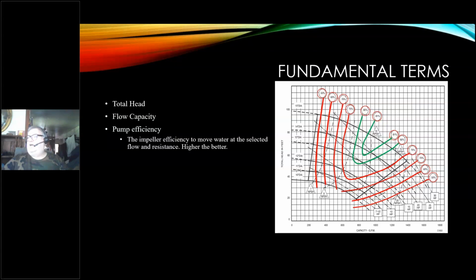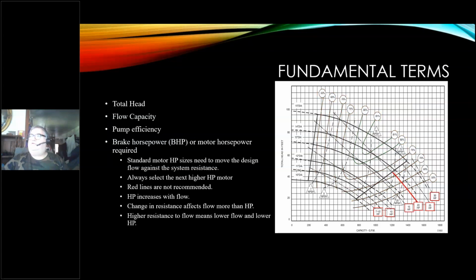Pumps are non-positive displacement, in these cases centrifugal. So in other words, every turn of the impeller doesn't move 100% of the water. In this case, 81% is the best we can expect out of this pump. And it falls off from there, of course, according to which size you use and how much your flow. Again, the resistance is going to matter. It moves the efficiency curve to the left. And with the amount of flow, eventually you get to the point that you can't move the water efficiently, and it moves to the right. So that's why these curves show up on both sides of the curve, towards the higher head and the higher flow.